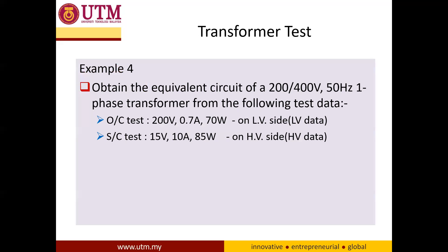For example four, we obtain the equivalent circuit of a 200/400 volt, 50 Hz single-phase transformer from the following test data. For the open circuit test, the readings of voltage, current, and power are taken from the LV side, which is now the primary. For the short circuit test, the primary side is short-circuited and the readings are obtained from the secondary side, which is the 400 volt side.